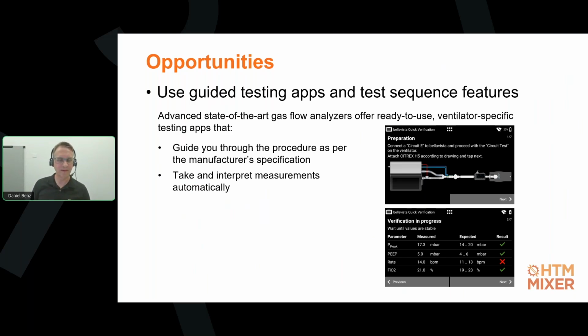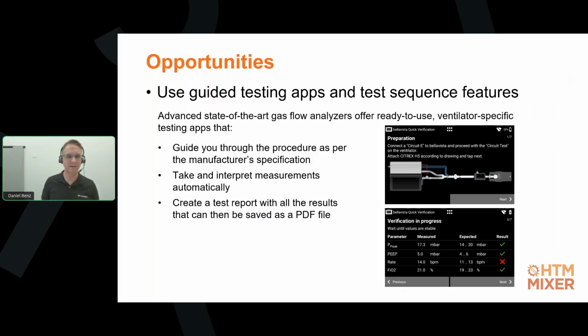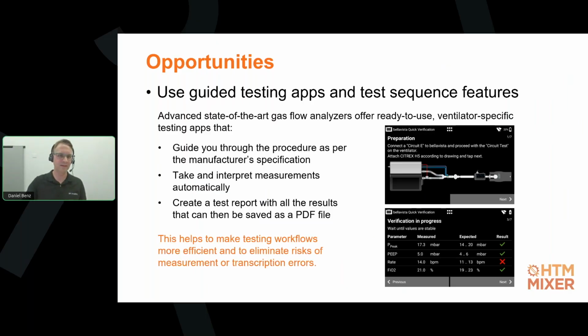Also, these applications and test sequences typically create test reports at the end, including all the results, that can then be saved and exported as PDF files. Besides making workflows more efficient, it also eliminates the risk of measurement and transcription errors. And it ensures that all the device settings, such as gas type, gas standard, and trigger settings, are correct for the device under test, because this is already programmed into these sequences.